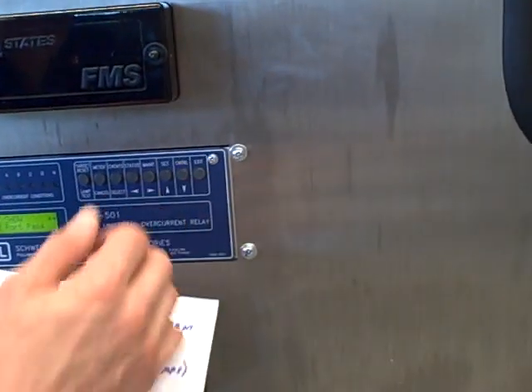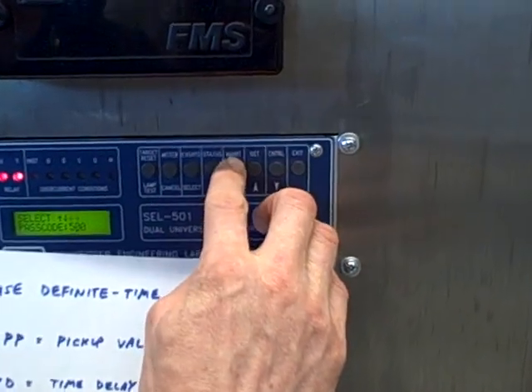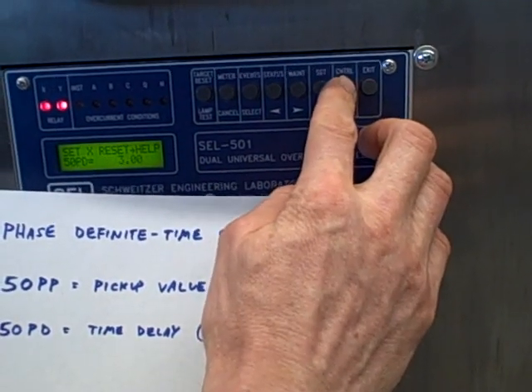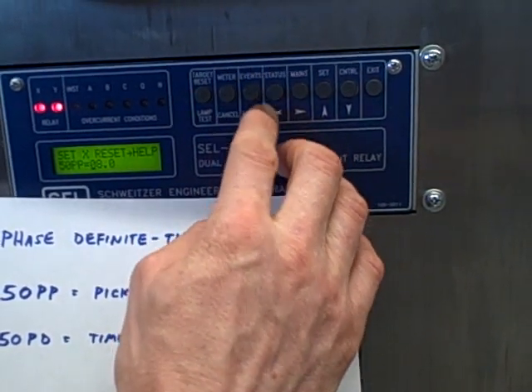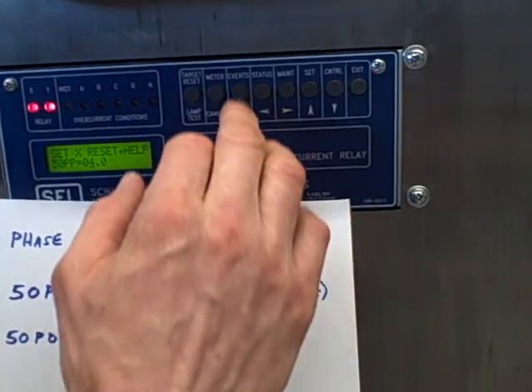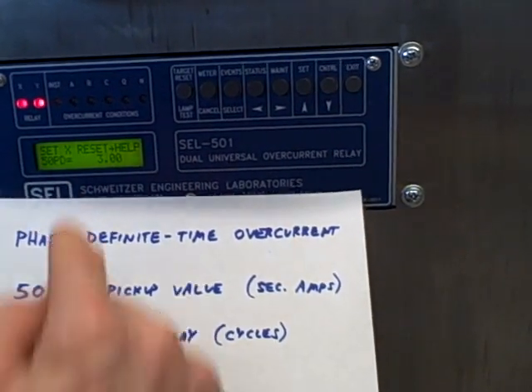We're going to go over here and set Relay X. We'll enter the passcode, which by factory default is 500. We step down into the menu and look for the parameter 50PP. Currently it's set at 8 amps. I want to set that at a low enough value where the vacuum cleaner can actually trip it, so in this case I'm going to set it to 4 amps secondary, which is 16 amps primary at the vacuum cleaner. Now the time delay — currently this is set to 3 cycles of the AC power.